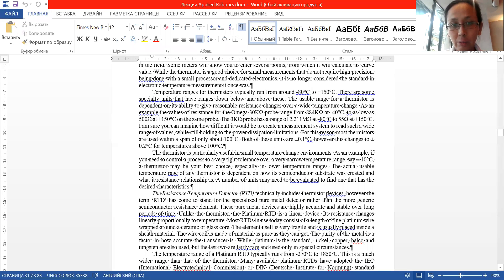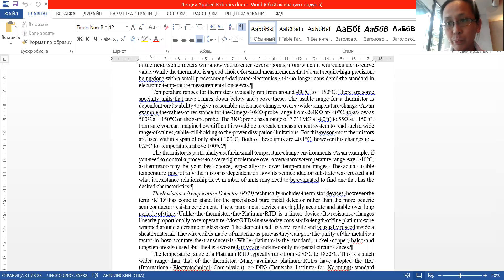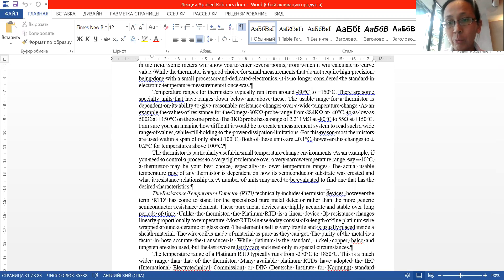The next device is a resistance temperature detector, or RTD. They usually include thermistor-type devices but are more advanced because they use pure metals — for example, platinum. That is why they are more accurate. RTD devices use pure metals like platinum, so they are more precise but, correspondingly, more expensive.